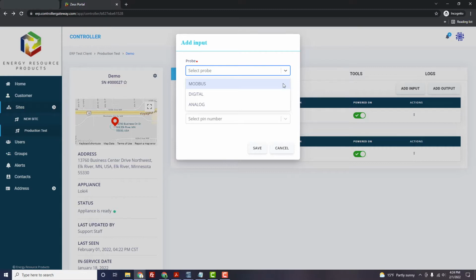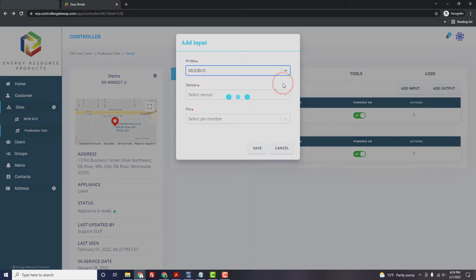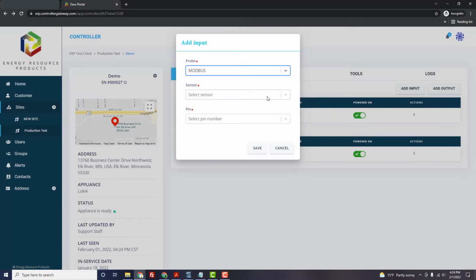From the Add Input, select the probe. We will select Modbus. The controller will communicate to the attached probe to identify it. After the blue buttons clear, the probe will be available in the drop-down. In our example, we are programming a conductivity probe.